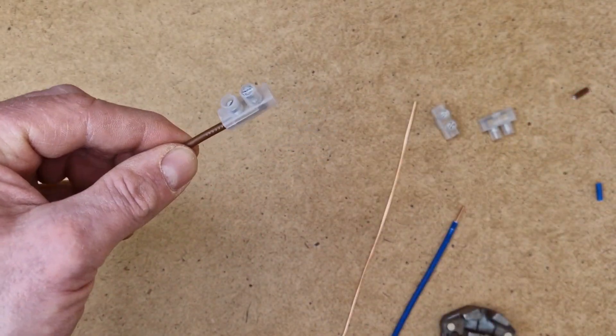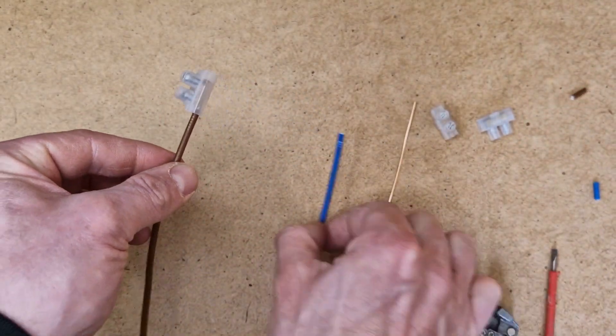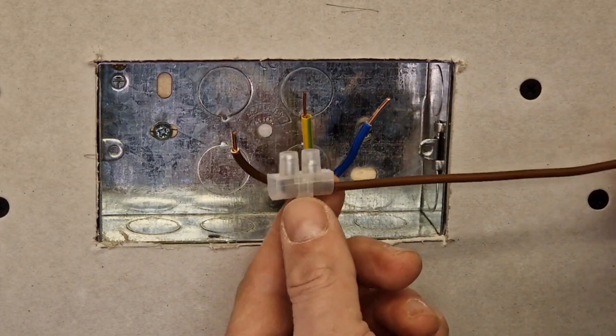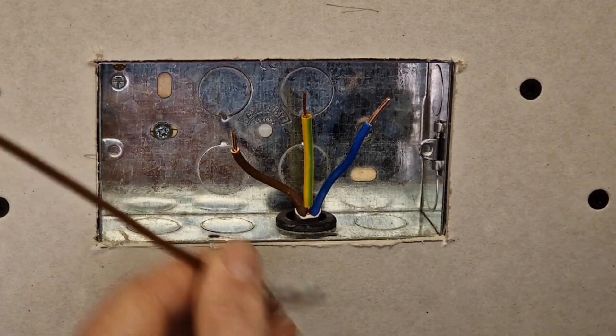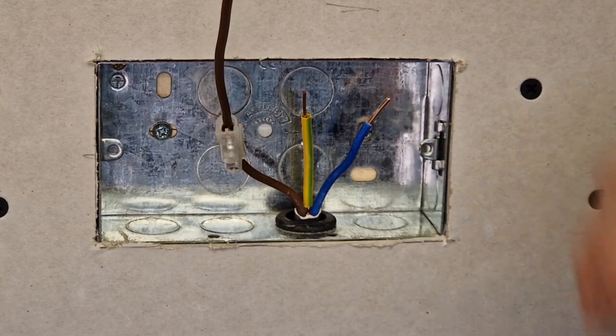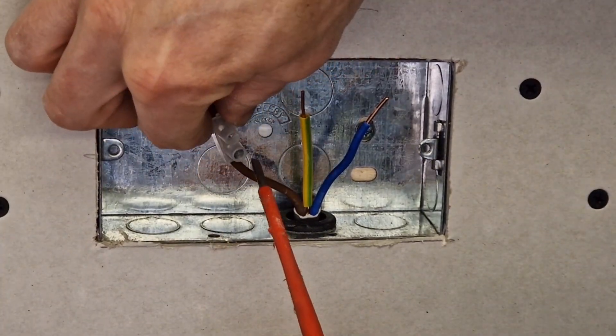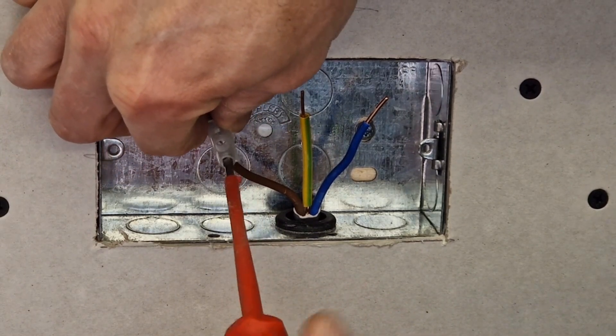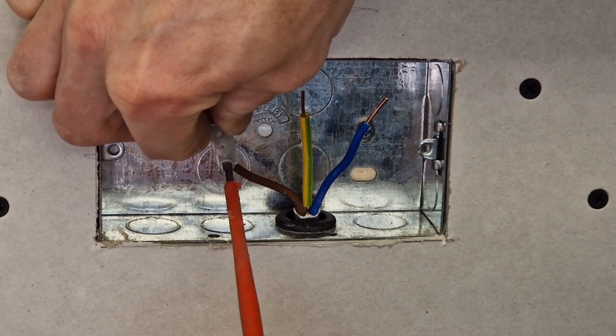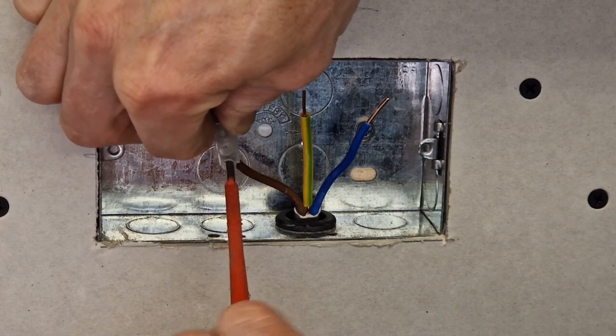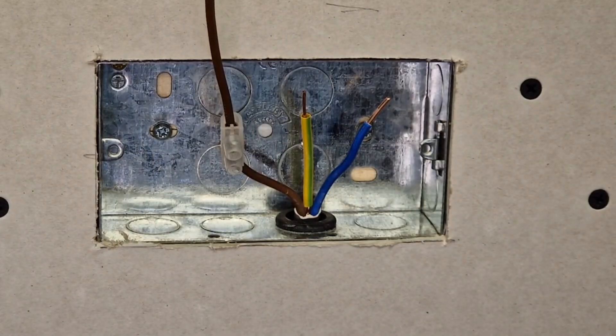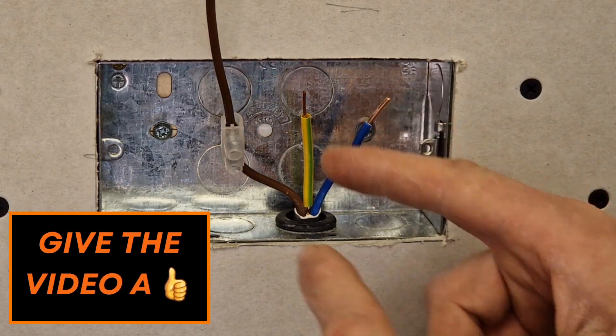So now we've got these cables with the connector blocks on, we can now attach them onto the existing conductors within the box itself. Same thing again, just tighten them up. Don't over-tighten them because that will compress the copper and potentially cause a high resistance joint or the cable could simply snap. Do the same method for each of these.